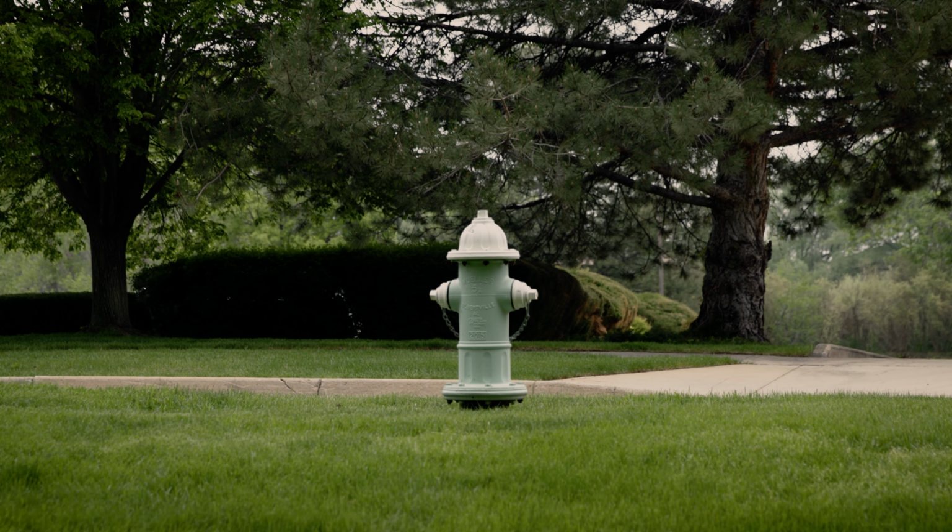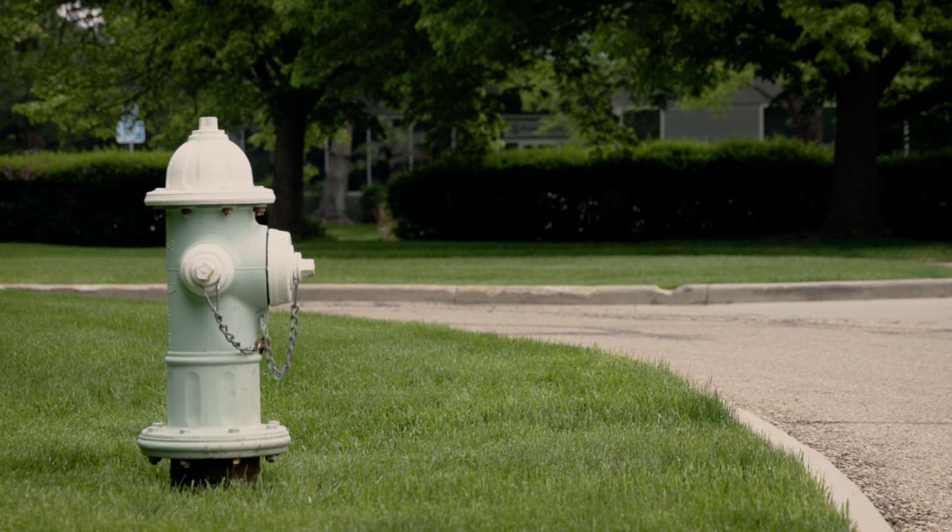We also need to make sure that we have access at least 3 foot around any fire hydrant. That's very important. We might not have the fire hydrant on the property. Fire hydrants are typically designed by the municipality or the local jurisdiction, and they were installed during construction, usually every 500 or 1,000 lineal feet, but we need to make sure we have that. And I usually take a picture. In this case, I'll have a fire hydrant that might be 300 or 400 foot away. I just take a picture of it, make sure it's open 3 foot around all sides.